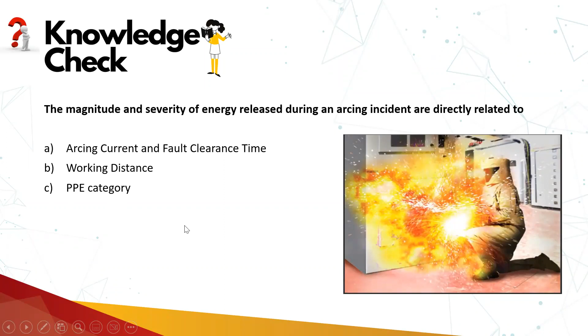But the energy released from this equipment will depend upon the available fault current and the fault clearance time, and the energy which is reaching this person, the incident energy, will be dependent on the working distance. If this person is sitting 10 feet away, the incident energy will be only 1.2 cals per centimeter square. But if he's working at the face of this electrical equipment, the incident energy might be 40 cals per centimeter square.